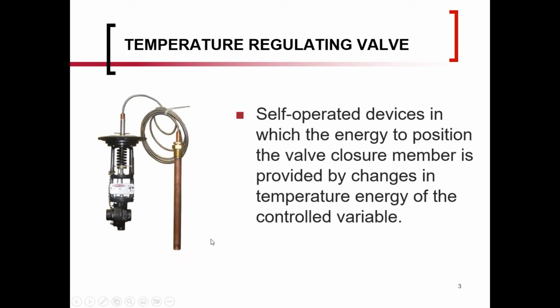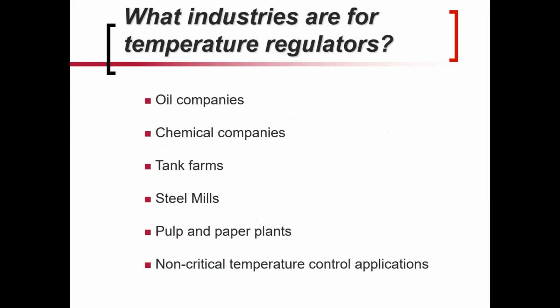So here's a very wordy definition of what a temperature regulating valve is. A self-operated device in which the energy to position the valve closure member, in this case a plug or a seat, changes based on the temperature energy of the control variable. What all those words mean, the most important part of this, is they're mechanical devices that open and close, or if sized correctly and applied correctly, they'll modulate based on the temperature of whatever it is that you're controlling. It can be a cooling application, it can be a heating application, it can be a tank, heat exchanger, whatever it might be. But the main takeaway for the definition is that it's a mechanical device for temperature control.